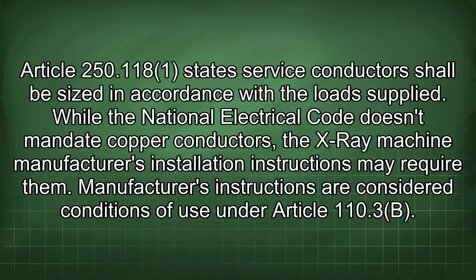Article 250.118 states service conductors shall be sized in accordance with the loads supplied. While the National Electrical Code doesn't mandate copper conductors, the X-ray machine manufacturer's installation instructions may require them. Manufacturer's instructions are considered conditions of use under Article 110.3(B).